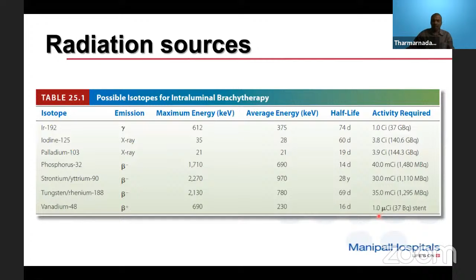As I told, energy is not that important as regarding the photon sources like iridium 192, iodine 125, and palladium 103. You can see here when we normalize the dose at 1 centimeter, 1 millimeter, then iridium 192, iodine 125, palladium 103, even though their energies may vary quite a lot, their dose fall off along the radial distance is almost more or less the same. So energy is not that important.